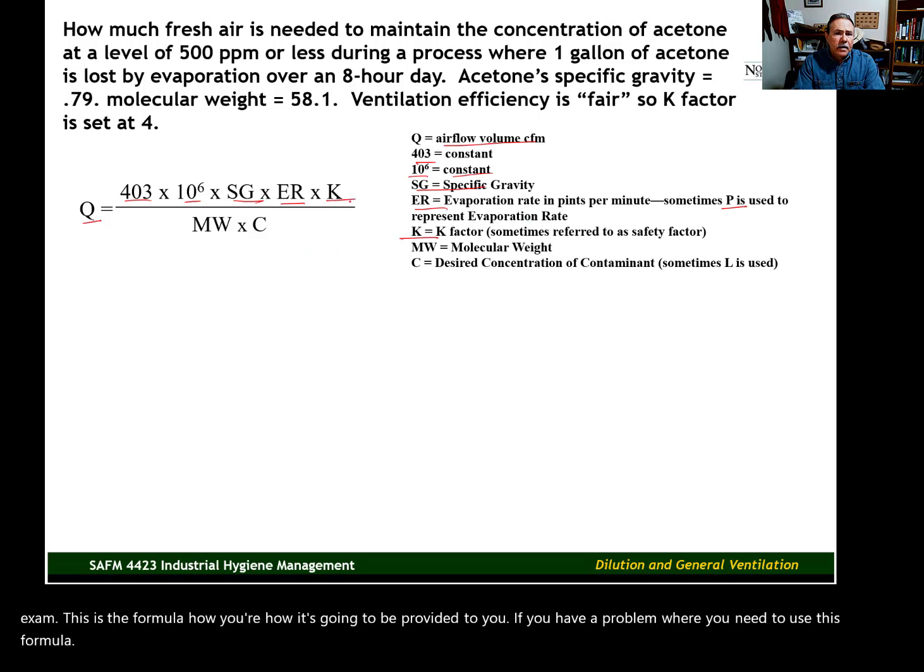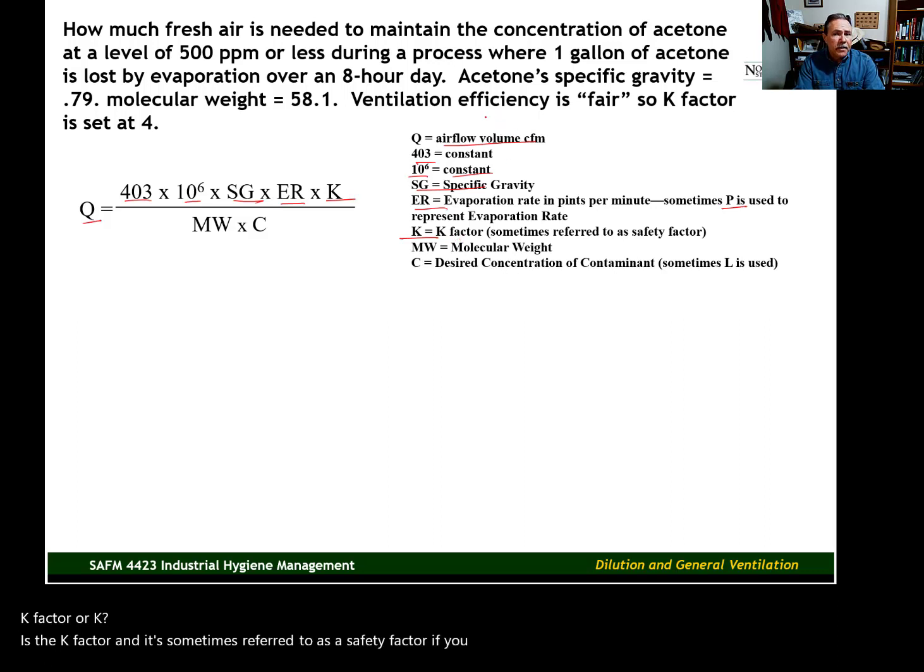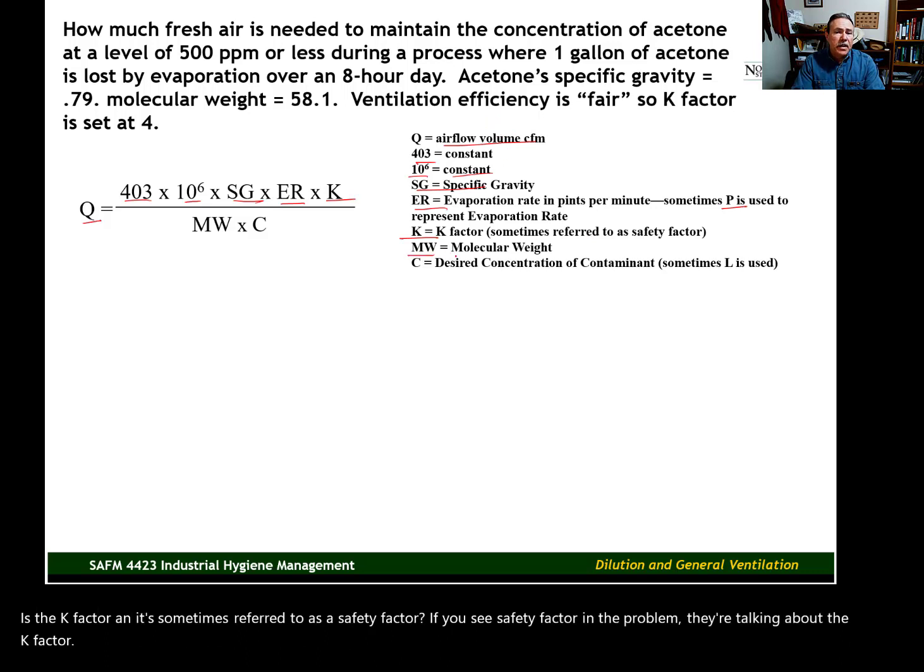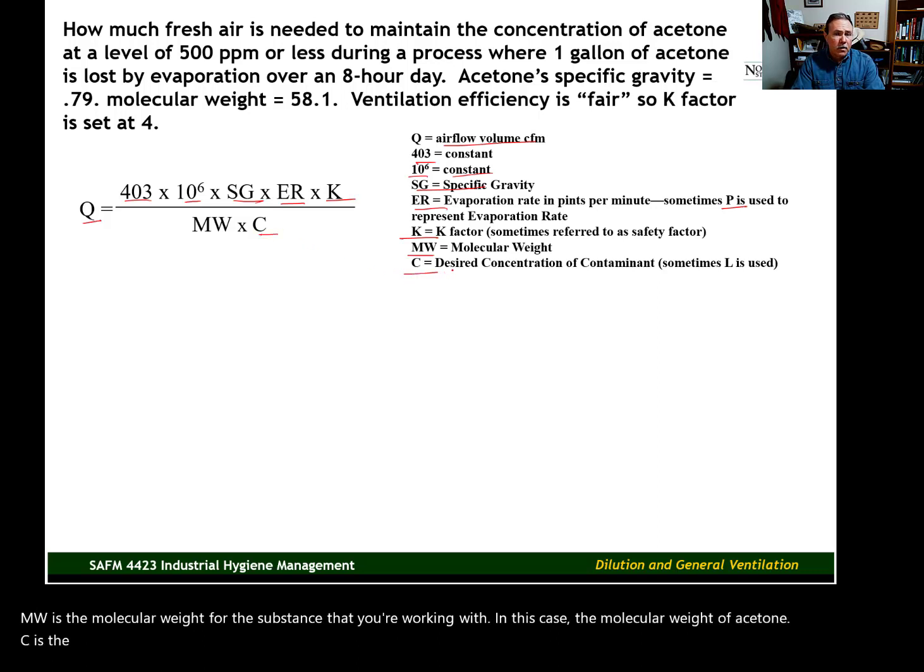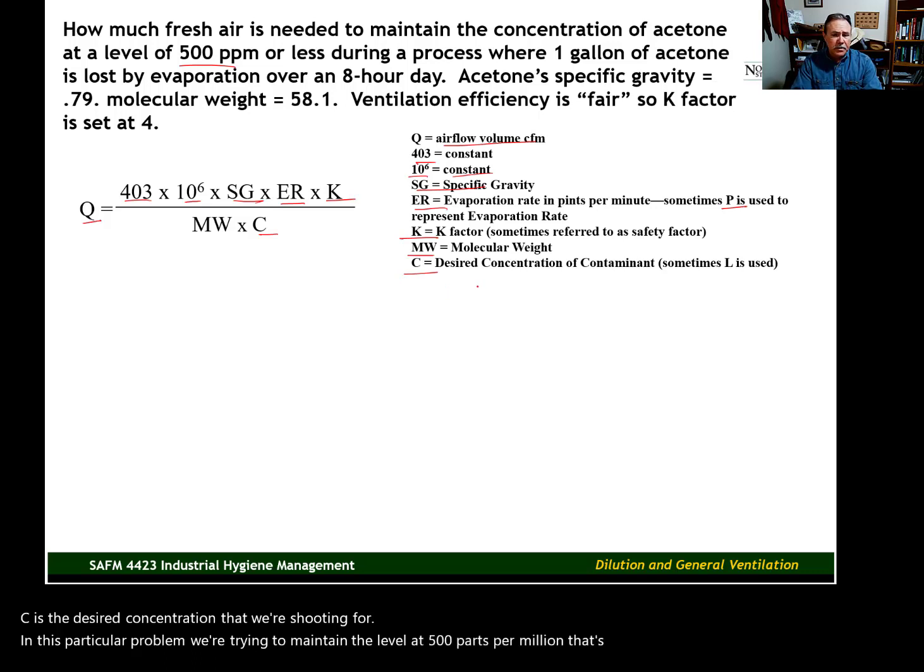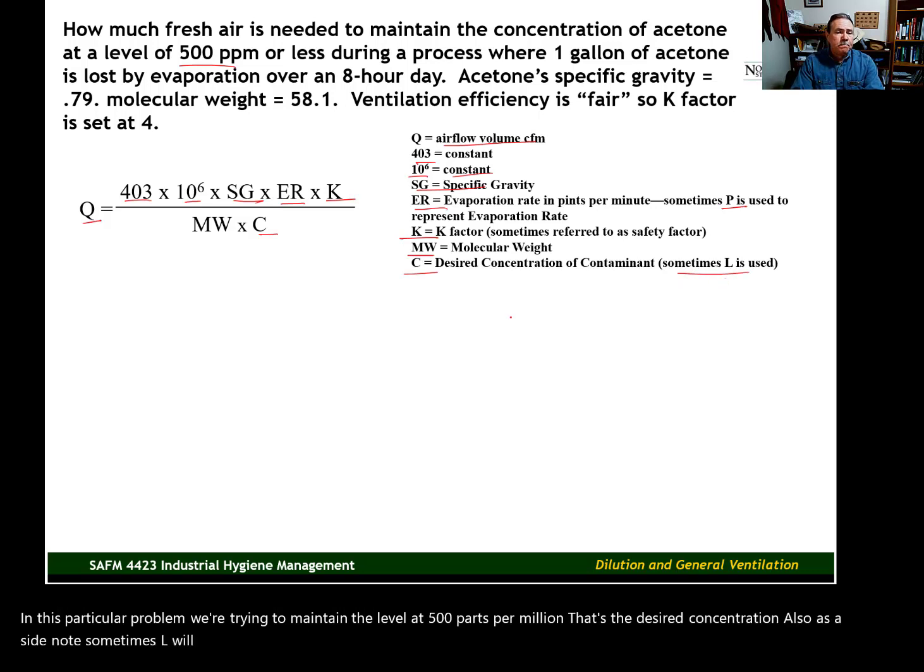K factor, or K, is the K factor, and it's sometimes referred to as a safety factor. If you see safety factor in the problem, they're talking about the K factor. MW is the molecular weight for the substance that you're working with. In this case, the molecular weight of acetone. C is the desired concentration that we're shooting for. In this particular problem, we're trying to maintain the level at 500 parts per million. That's the desired concentration. Also, as a side note, sometimes L will be used in place of C.